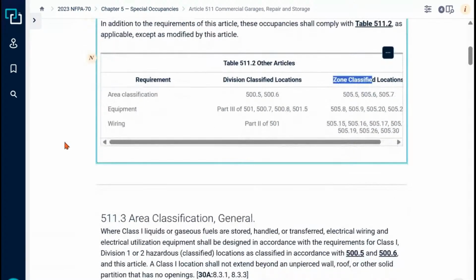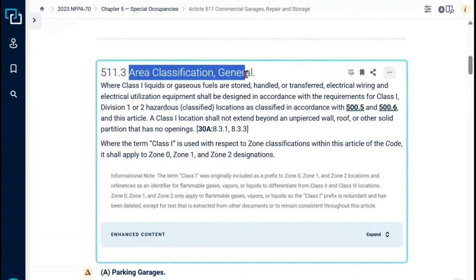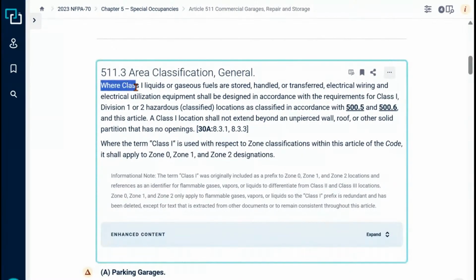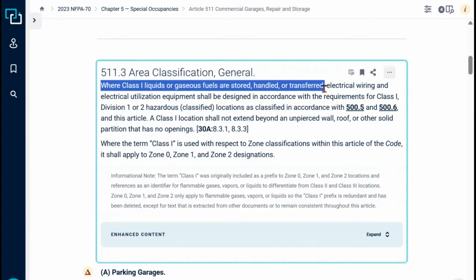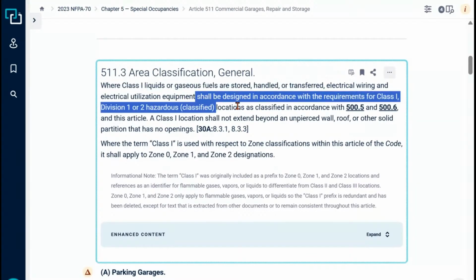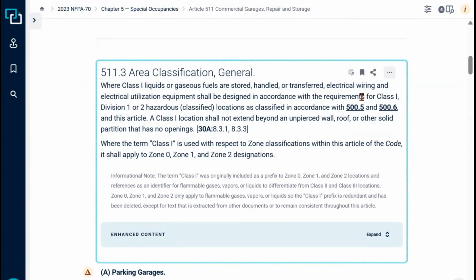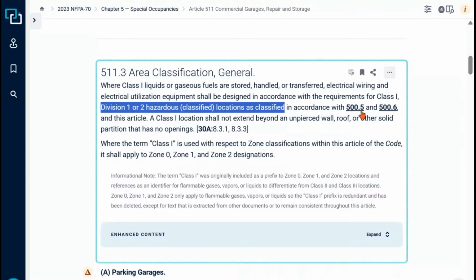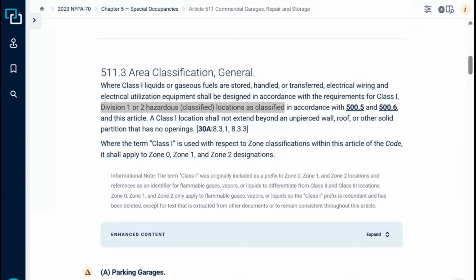Area classification in general: where Class 1 liquids or gaseous fuels are stored, handled, or transferred—remember, we're talking about commercial garages now—electrical wiring and electrical utilization equipment shall be designed in accordance with the requirements of Class 1, Division 1 or 2 hazardous locations, per 500.5 and 500.6. So remember, we've got to go all the way back to 500, right? It's not just that it says that here.